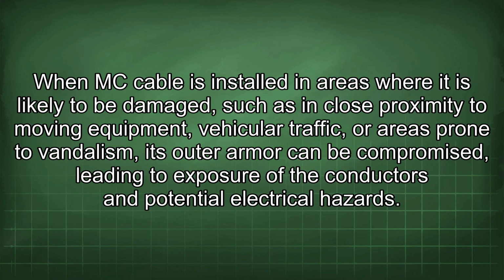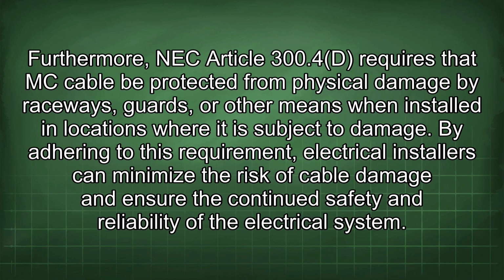When an MC cable is installed in areas where it is likely to be damaged, such as in close proximity to moving equipment, vehicular traffic, or areas prone to vandalism, its outer armor can be compromised, leading to exposure of the conductors and potential electrical hazards. Furthermore, NEC Article 300.4d requires that MC cable be protected from physical damage by raceways, guards, or other means when installed in locations where it is subject to damage. By adhering to this requirement, electrical installers can minimize the risk of cable damage and ensure the continued safety and reliability of the electrical system.